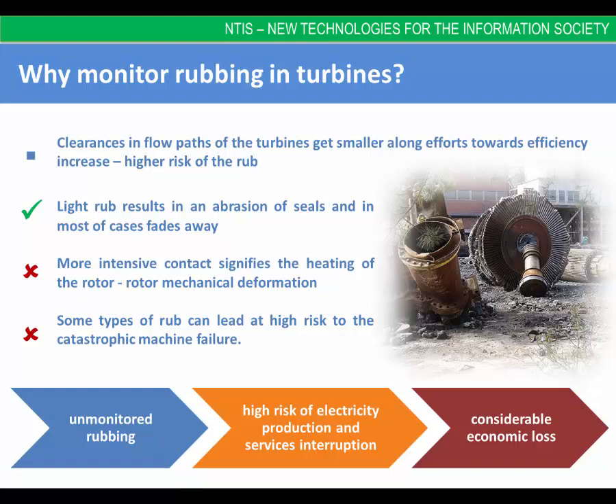Very often the light rub results in an abrasion of seals and in most cases fades away. It begs the question: why monitor rubbing in turbines? The answer is that the rest of rub cases are a serious malfunction of the machine and can lead at high risk to catastrophic machine failure. More intensive contact causes heating of the rotor at the contact location and results in rotor mechanical deformation. In some cases the rub may rapidly deteriorate and cause catastrophic breakdown if not early detected, interrupting electricity production and resulting in considerable economical loss.